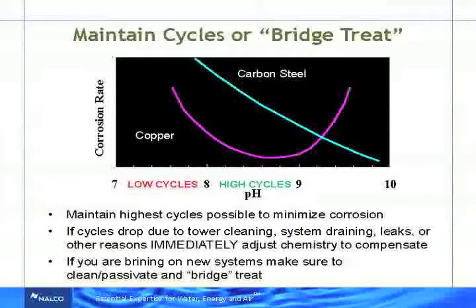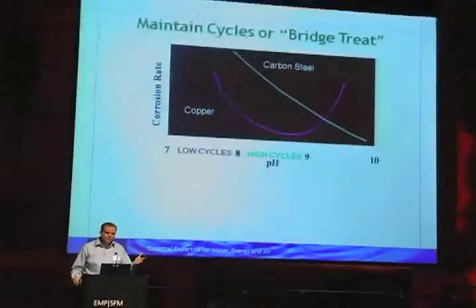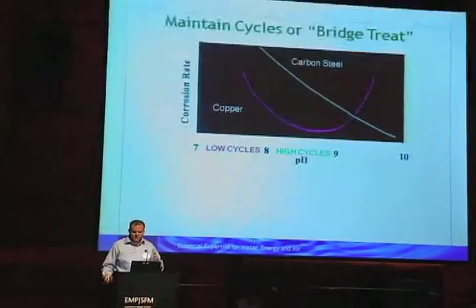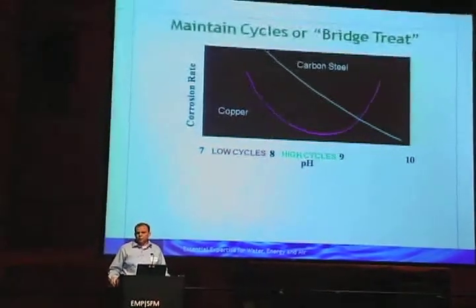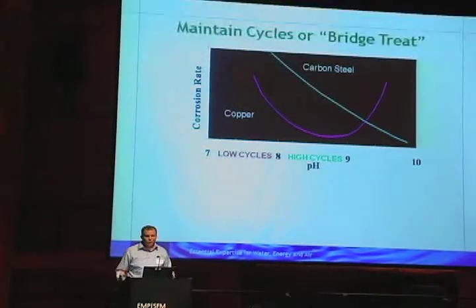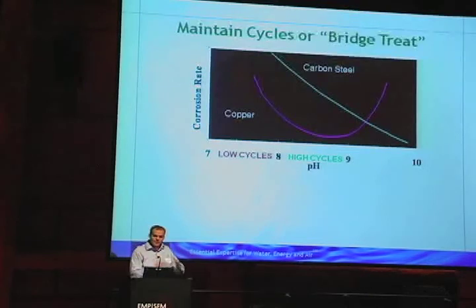So when you're running fresh city water in there, you're in a low cycle region. If you're probably below, I'd say, 4 or 5 cycles, you're going to be below 8 in your pH. So you're going to be a lot more corrosive. What you want to do, and a lot of your corrosion prevention will help you do this, is run higher cycles. If you run 12, 13 cycles, you're going to be up towards 9. You're going to be able to really reduce that corrosion rate. That's why fresh city water causes so many problems, because it bumps that pH down and you get rapid corrosion because of it.